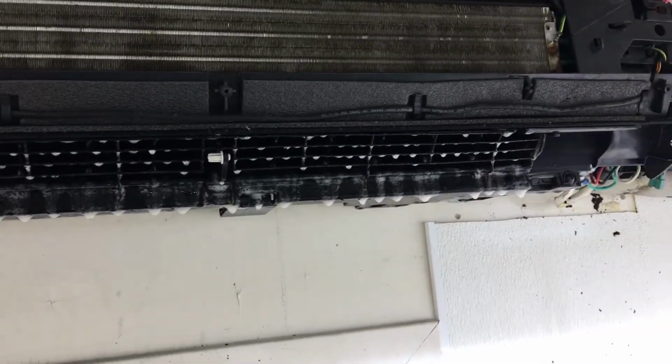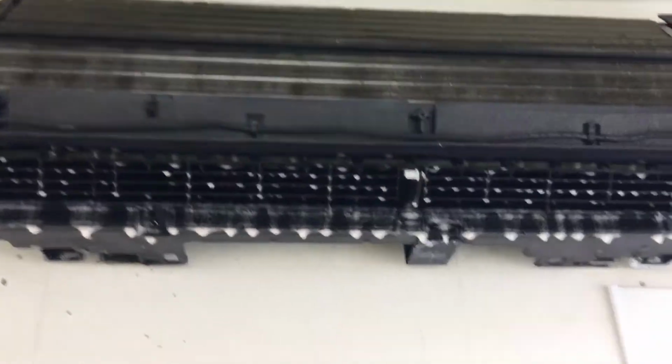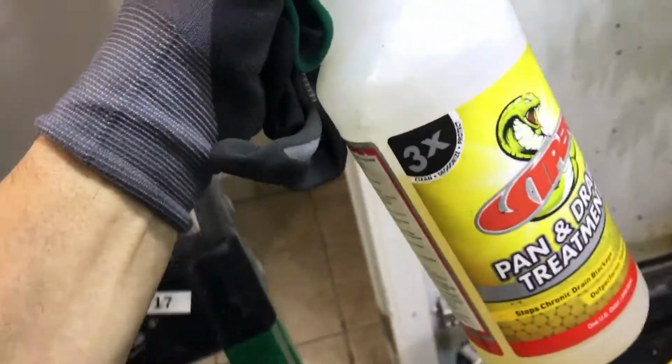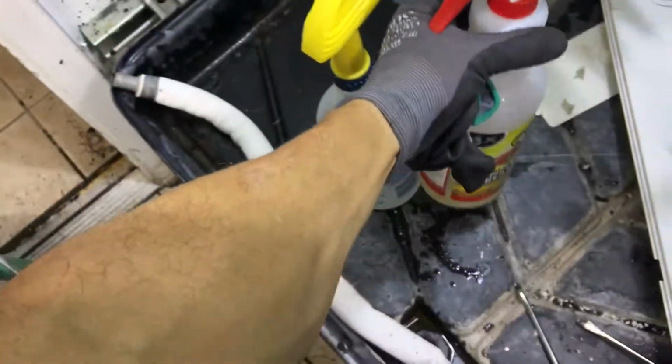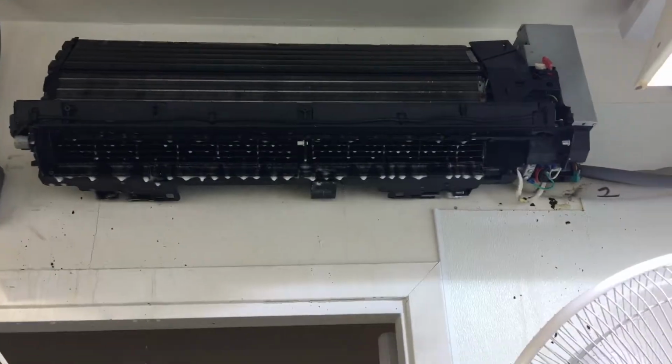You should see how much corrosion is on all the circuit boards. All the little resistors and caps and everything are all corroded, green and fuzzy. The solder joints look like they're ready to disintegrate. So that hopefully will extend its life. Get at least 6 more months, a year out of these units before just replacing them. That's it.